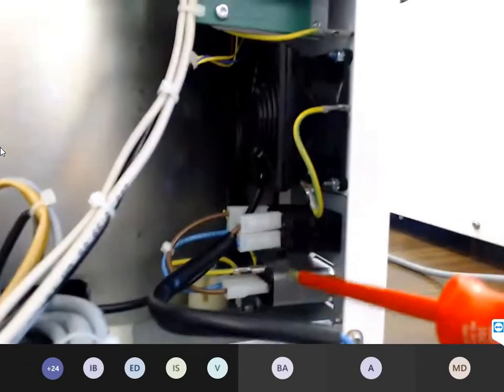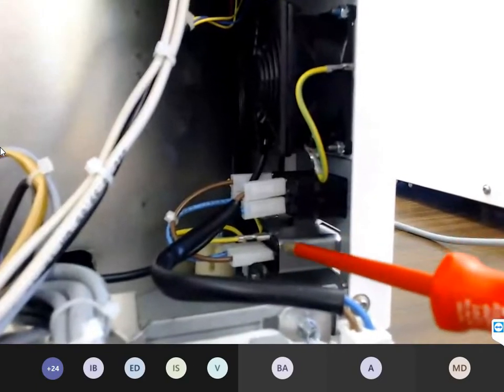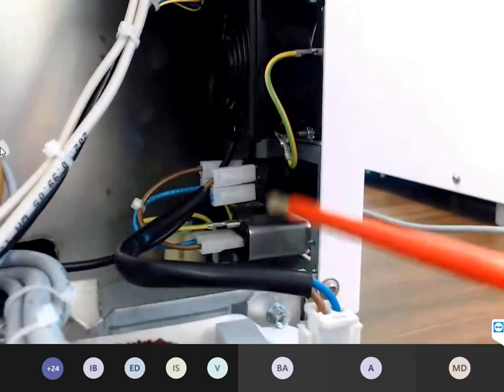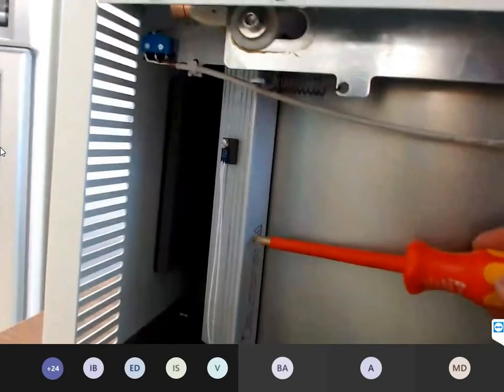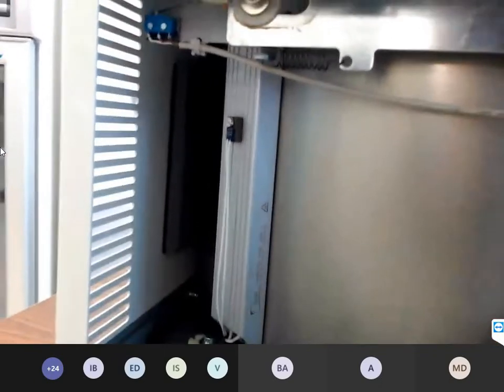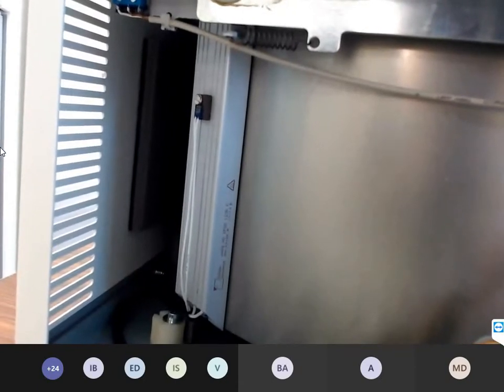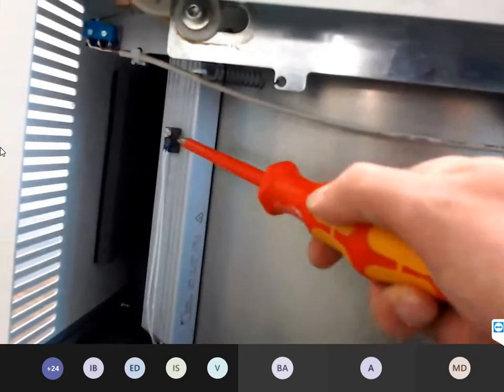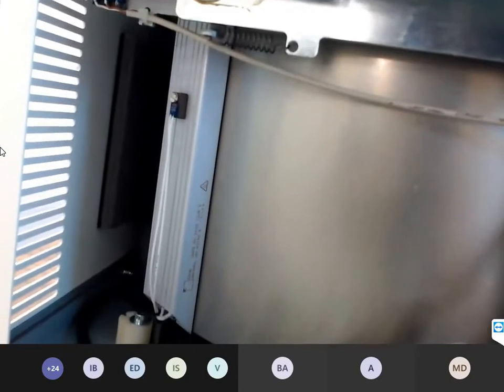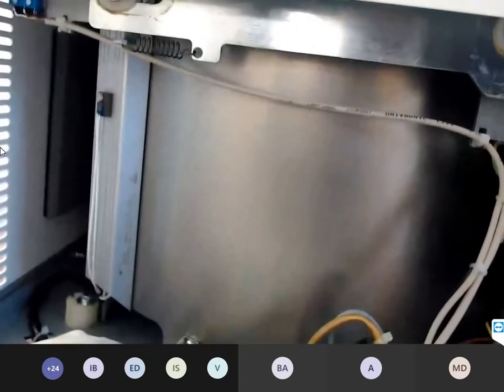And yeah, we have here the filter for the power input, here the switch, and on the left side the braking resistor is the over temperature switch for the braking resistor. It's a bimetal switch. It means in case of over temperature, the switch goes open, you get an error message, and in this case you have to wait for 10 minutes, and then you can switch off, switch on the device again. It works, it's fine, it doesn't work. You make a troubleshooting or change components.